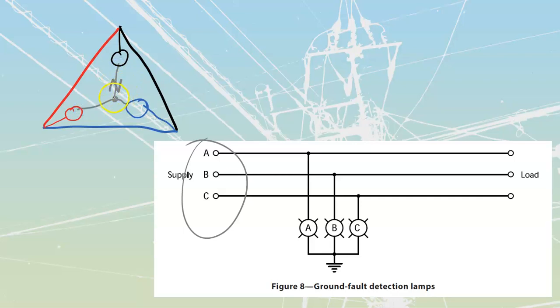We tie that common point down to actual ground. If this was a 600 volt delta system, by virtue of the lights being connected in a Y, each light would be operating at 347 volts, so they'll be glowing somewhat dimly.